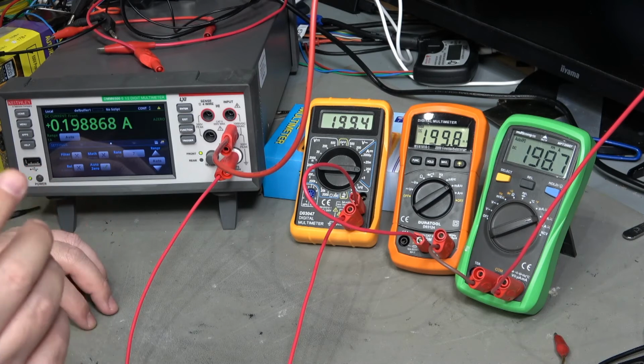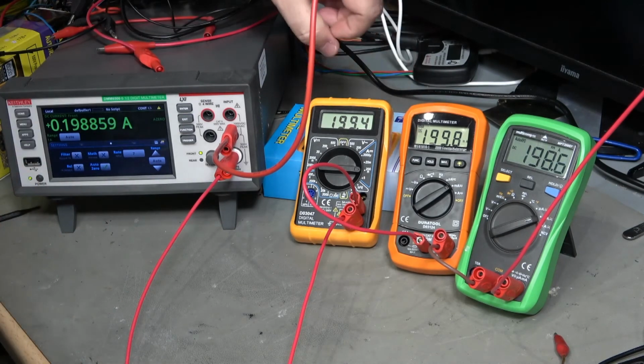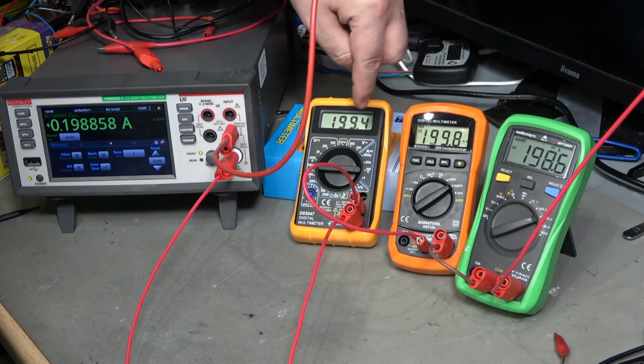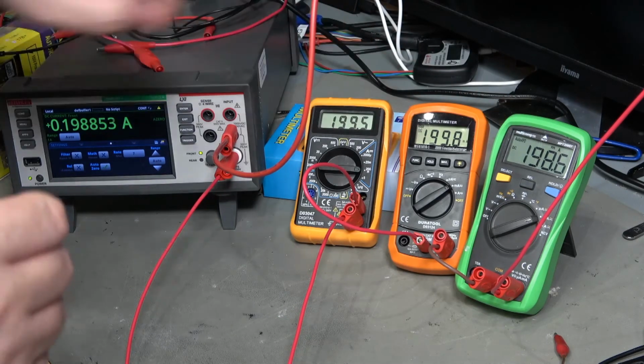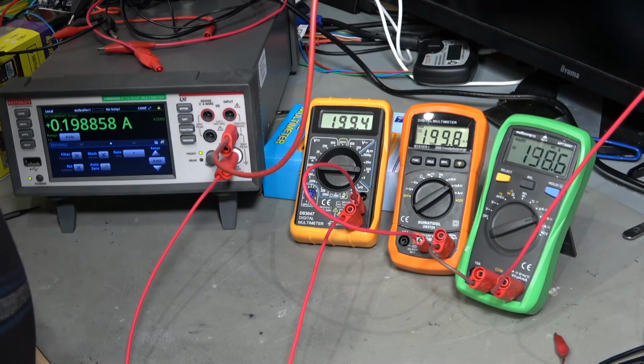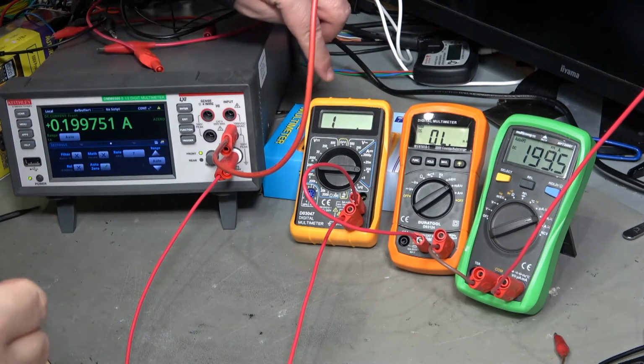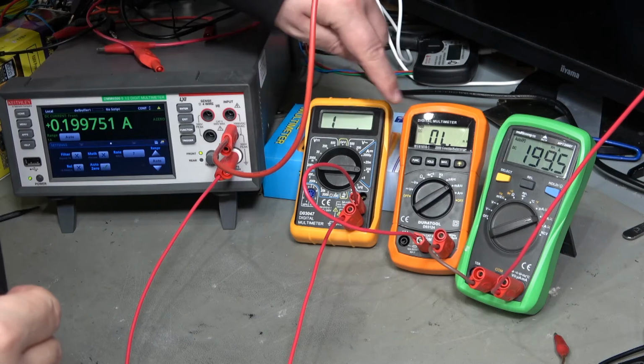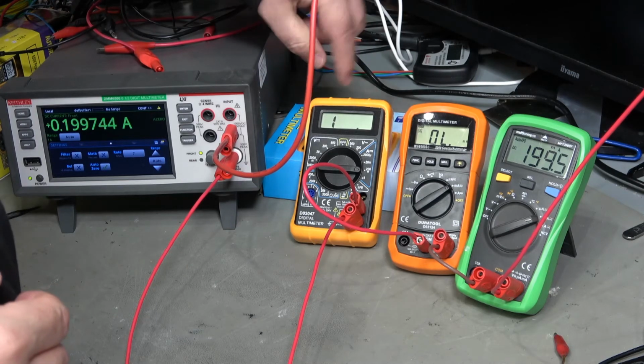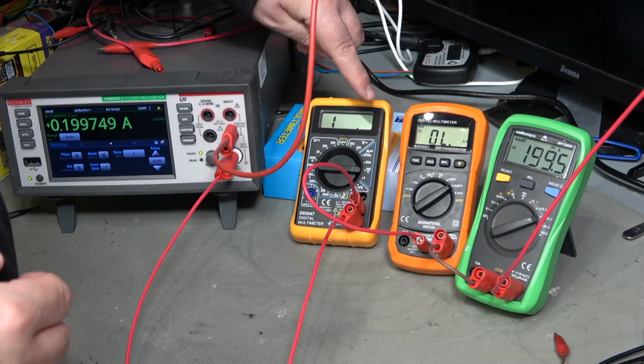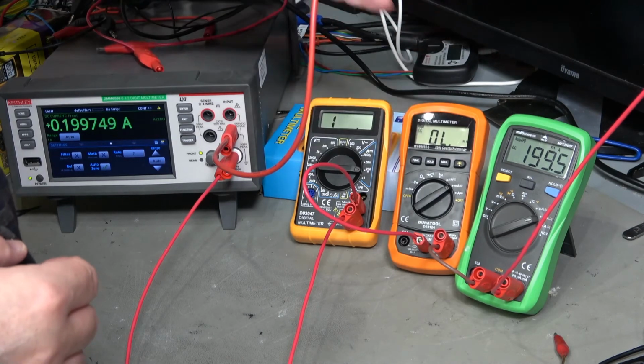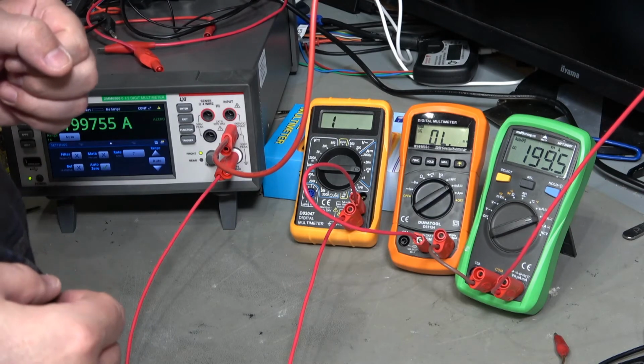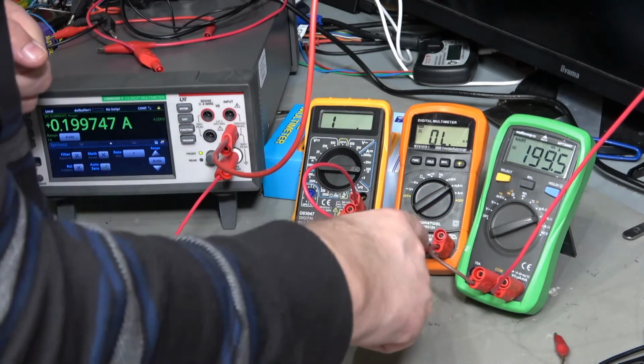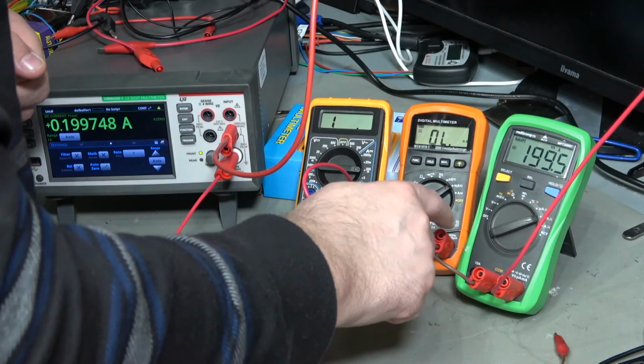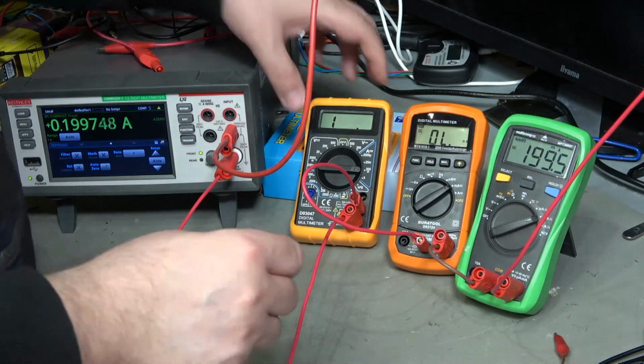So really accurate. So the reason I chose 199 is to put these right close to what I think will be the cut-off limit for this one. So I just want to see what happens if we push that current up too high. Oh, there we go. So both of these can only have a 1 in the left-hand digit, and both of them are attempting to display a 2. This one's just kind of showing an error display. This one's showing OL for overload. So that's fairly straightforward. So we can move this plug from the milliamps across to the amps, would be how to solve that.